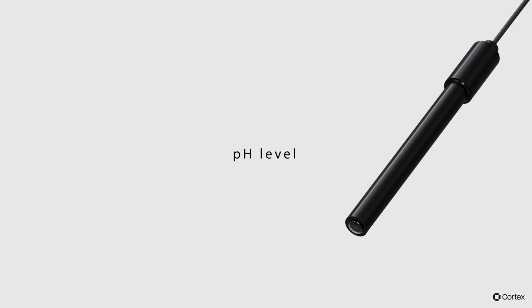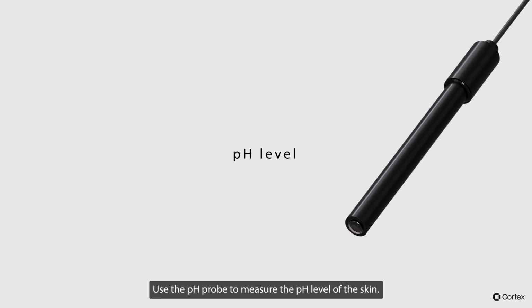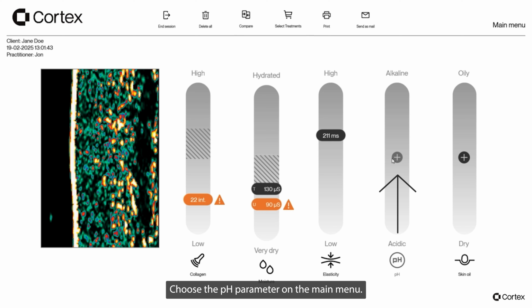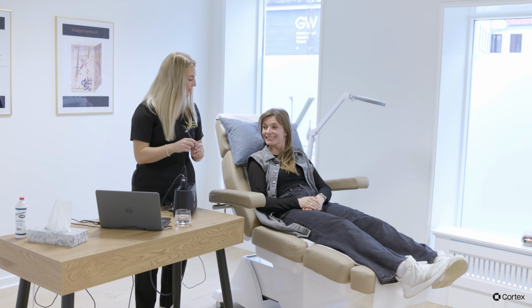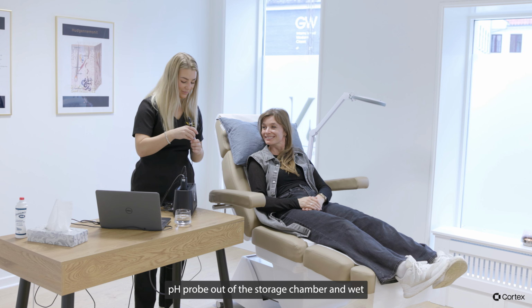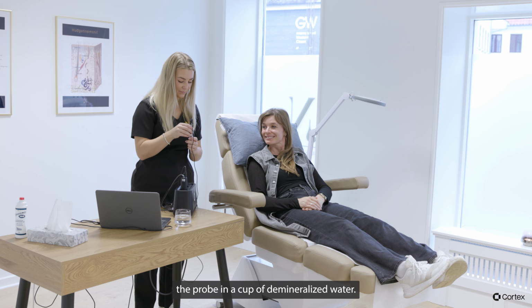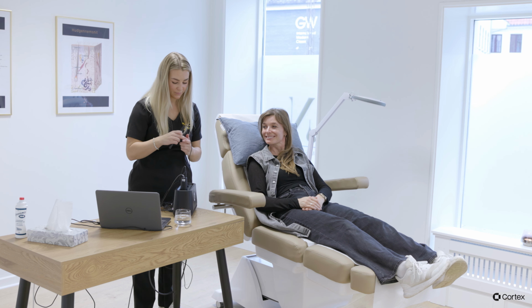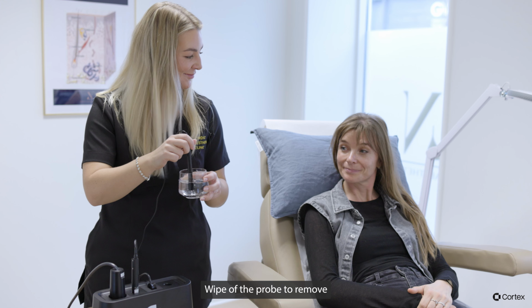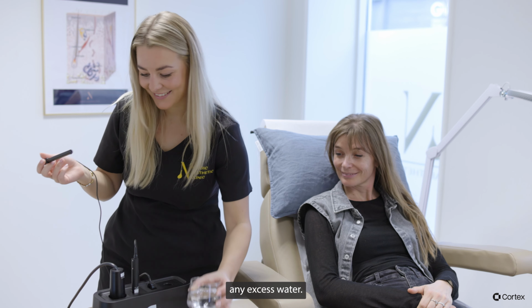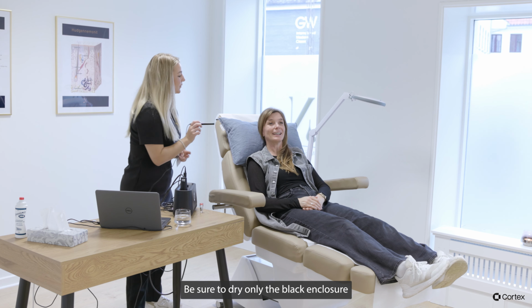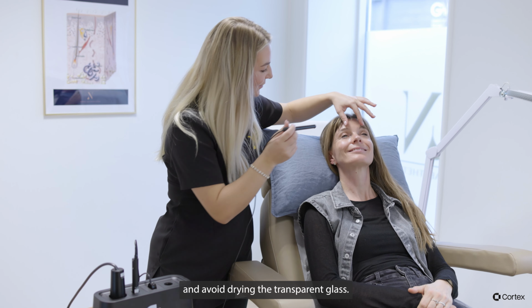Measurement of pH level. Use the pH probe to measure the pH level of the skin. Choose the pH parameter on the main menu. Take the pH probe out of the storage chamber and wet the probe in a cup of demineralized water. Wipe off the probe to remove any excess water. Be sure to dry only the black enclosure and avoid drying the transparent glass.